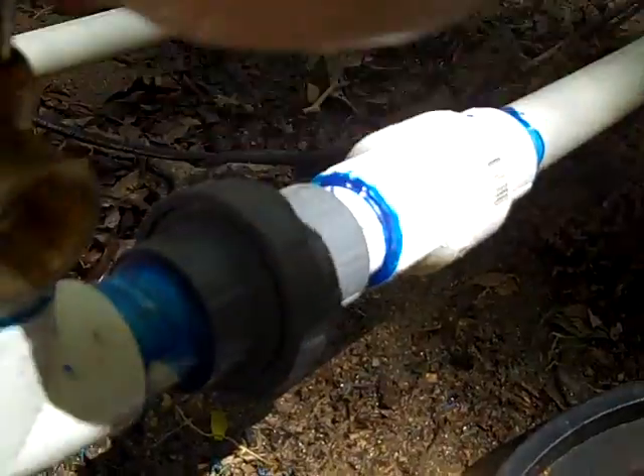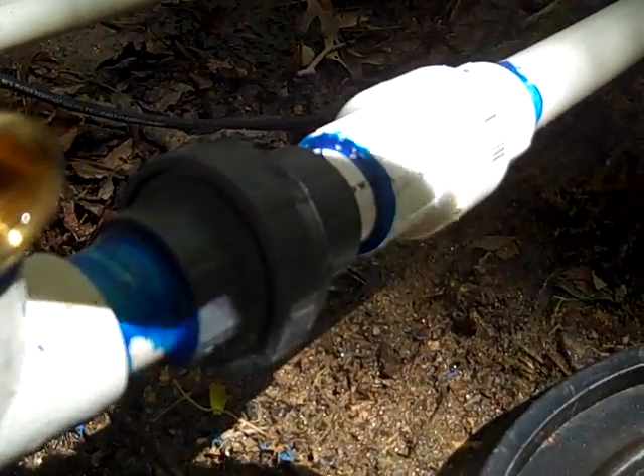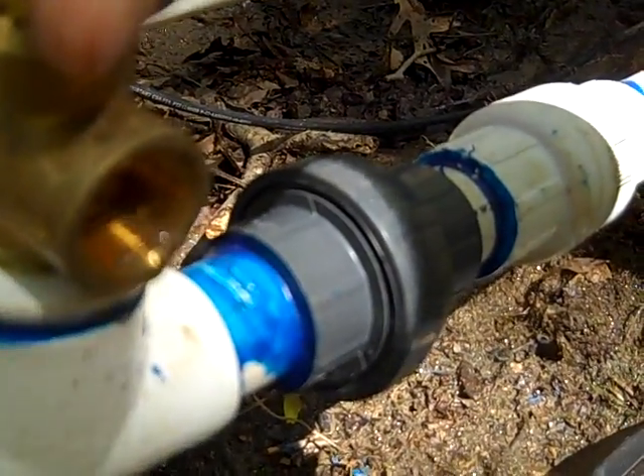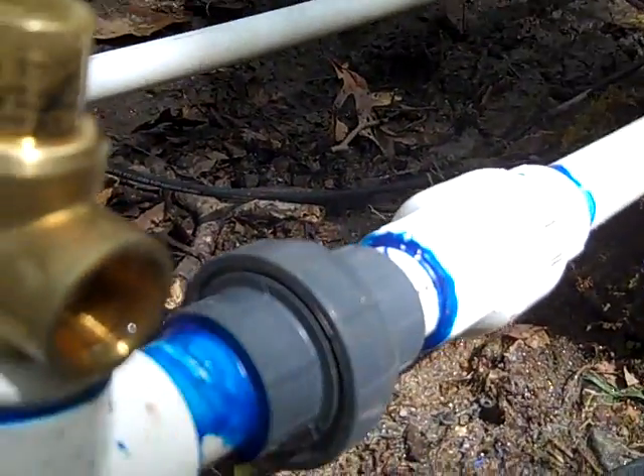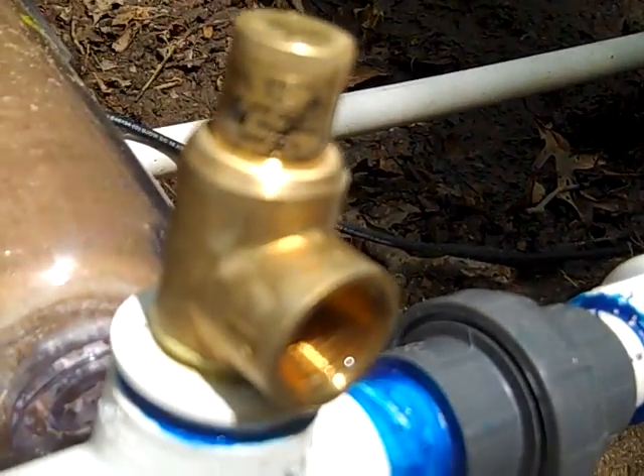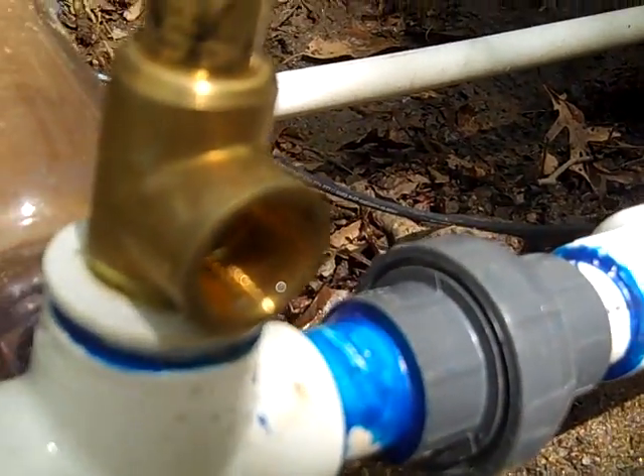I'll crank this down so the water is just barely coming out. I am pumping to my final destination, so I'll back off a little bit. If the pipe froze upstream, pressure would build and it would blow off right here, which will save my pump. So another fail safe gizmo — this is a manually adjusted pressure relief valve I picked up from Grainger's.